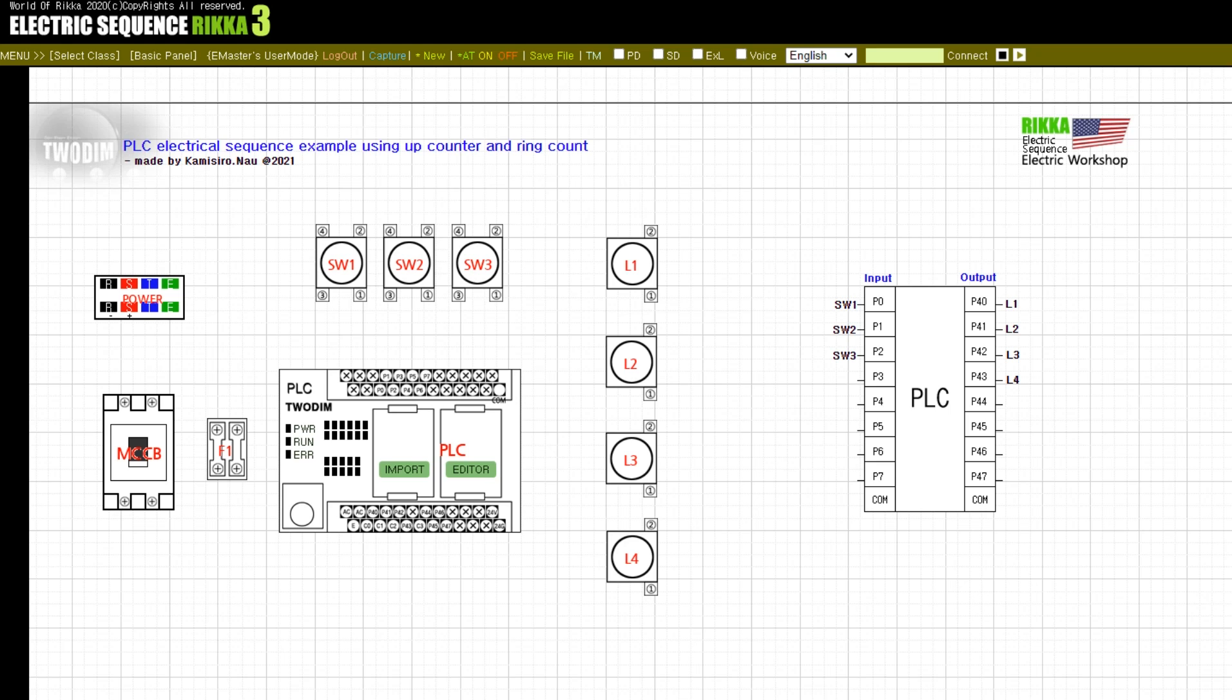Output lamps L1, L2, L3 are controlled via SW1 and SW2 push buttons. L4 turns on and off via SW3 push button. For the operation configuration, look at the PLC ladder configuration briefly explaining the operation. Each time the push button SW1 is pressed, the L1, L2, and L3 lamps turn on sequentially, and the L3, L2, and L1 lamps turn off in reverse through the SW2 push button.